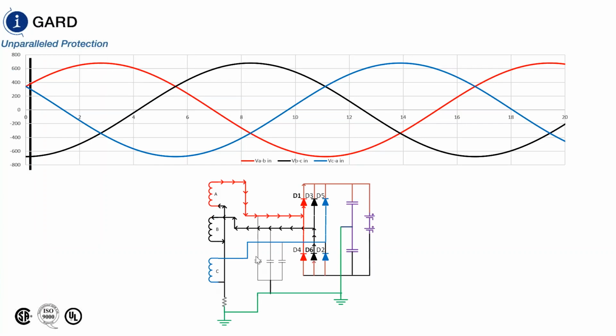Right. And if you look on the screen, you can see the front end. A lot of people put MOVs on the front end and EMI capacitors. So basically what some drive manufacturers believe is that ground is this miraculous place that can just absorb all unwanted frequencies. Yeah, that's not going to happen. And the MOVs are there so that you can protect the drive, so they would actually perform their job if you have an overvoltage. But with the resistance ground in the system, you're going to go to line potential with respect to ground when you have a fault on the system.